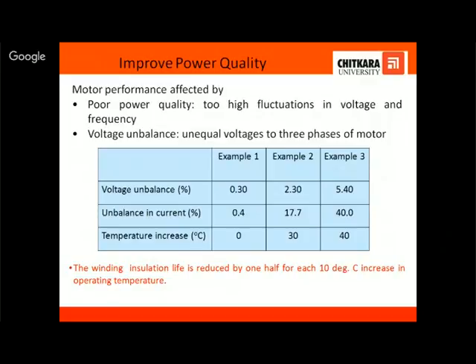If the voltage unbalance is 5.4%, the temperature rise is 40 degrees Celsius. And the winding insulation life is reduced by half for each 10 degrees Celsius increase in the operating temperature. So this is the effect of power quality on the performance of the machine. If there is an unbalance in the supply, it will result in a temperature increase, which will result in a lower insulation life of the motor.